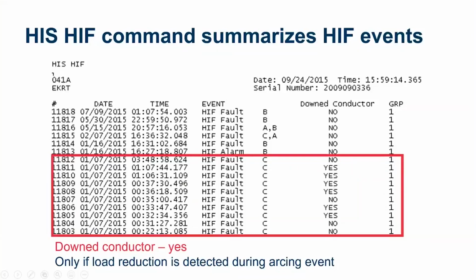So in order for the relay to detect or tell you if it was a downed conductor, it needs to see a certain amount of reduction in load. So if there was a certain amount of load and there is a down conductor condition, then you will see a reduction in load. And that's when the relay is going to assert this down conductor, saying, yes, I saw a reduction in load. But consider a lightly loaded feeder or a lightly loaded lateral. It could be possible that it doesn't have enough load so that the relay detects a loss in load or a reduction in load. So in that case, you might not get this assertion correctly. As Anthony mentioned, all HIF faults are not detectable. So what you do is use the integrated approach, using multiple different approaches to detect a down conductor. But again, this gives you a good indication if it's the actual down conductor or not, based on the load reduction.